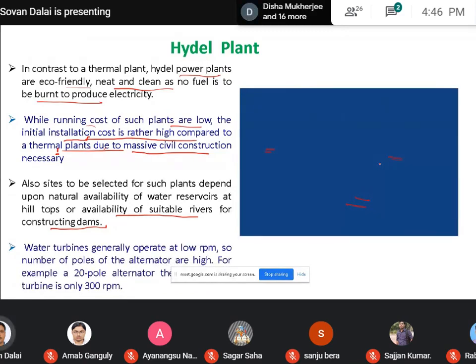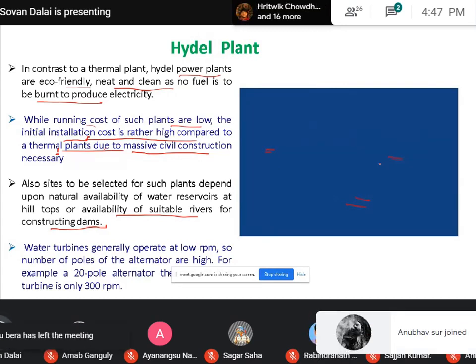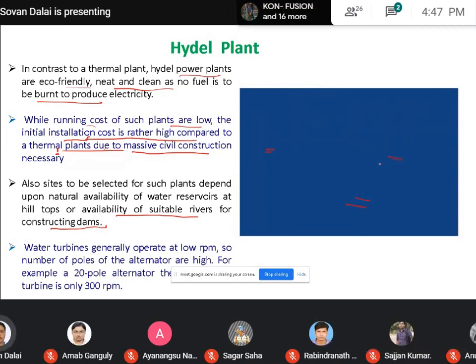Now, if you compare the hydel power plant alternator, generally the hydel power plant alternator runs at low speed, because here the water turbine generally operates at low RPM, so the number of poles of the alternator is very high, generally in the range of 20 poles. Normally, in the case of a thermal power plant, the number of poles of the alternator is in the range of 2 poles, and maximum you can get 4 poles. The RPM of the alternator is 1500 RPM if you consider a 4 pole alternator.